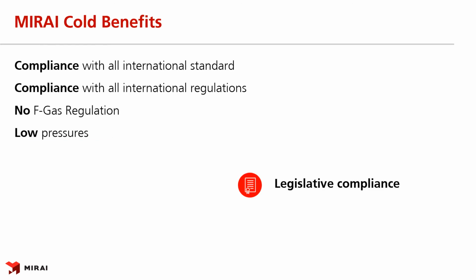When you use air as refrigerant, you will comply with all international standards and regulations. You will not be subject to F-gas regulation. Your system will work with very low pressures. For smaller machines, it is up to 4 bar, and for larger machines, it is up to 8 bar, so no more than a road bike tire.